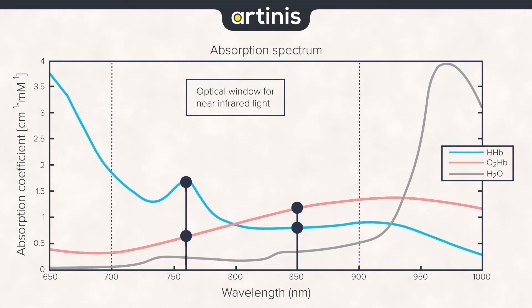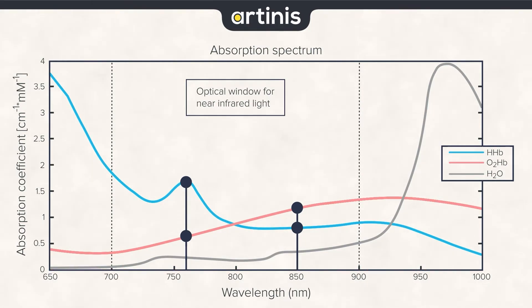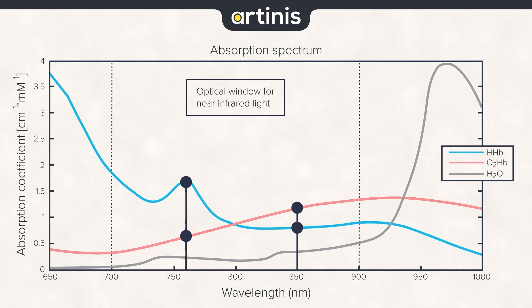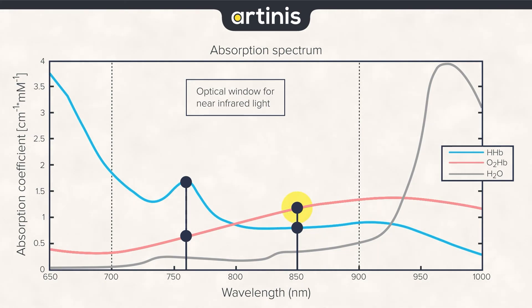Measuring differences in light absorption allows us to estimate concentration changes, thanks to the intrinsic absorption of light by specific chromophores. In this graph, the x-axis shows the near-infrared wavelength from 650 to 1000 nm, and the y-axis shows the absorption coefficient. We focus on two chromophores: oxyhemoglobin in red and deoxyhemoglobin in blue, because they can tell us about oxygen consumption. For our systems, we use two specific wavelengths: 760 nm, where deoxyhemoglobin is the main absorber, and 850 nm, where oxyhemoglobin is the main absorber.